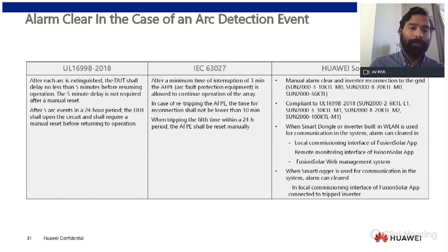This is why it is very important to have an accurate AFCI system, because as you can see, you can be a whole day without producing, which if you add this to several days in a year, it could be a significant amount of yield that you are losing. It is also important to have a fast reconnection system when you are allowed to connect remotely, and you can do this if you have our dongle or a smart logger with the inverters. A remote reconnection, or alarm clear, will be allowed and possible as well.